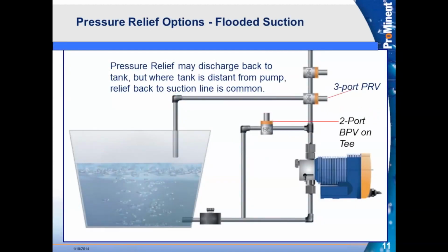In this slide, here you can see another variation of what I talked about. We're using the 2-port, truly a back pressure valve. It comes off of the T. We're using that as our pressure relief. So we simply adjust it higher than the back pressure valve, which is the very top valve that we see in this display. We have it adjusted slightly higher than that. So now if the system pressure exceeds, we can still pump into it up to where we have the pressure relief set to. Now that's going to open and it's going to feed back into the suction line. So that pump is going to stop building any more pressure into the system. So that's very critical to us.